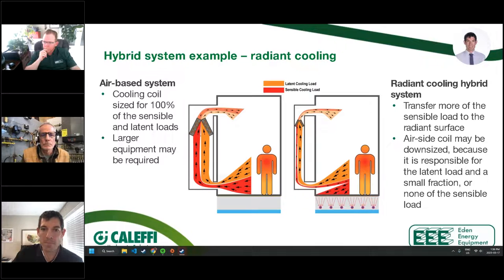You allow the radiant to be the one that's carrying more of the weight with the sensible load, and then you're still dealing with effectively the latent load with the A coil there. So that's essentially what you would do to have a split hybrid radiant cooling system and maintain the best of everything.